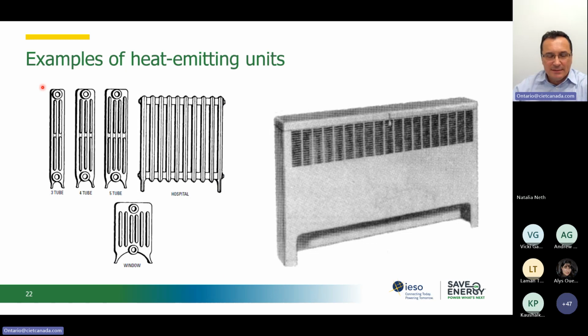which are cast metal, cast iron, and they provide a certain heat transfer function, but they are not very efficient in transferring the heat from the fluid that flows through these tubes to the air in the space. We've also seen an alternative to this where the heat exchanger has an improved heat transfer feature because we now have a flow of air that drives over the heat exchanger. So behind this case, we may see a fan that drives the air around the heat exchanger.